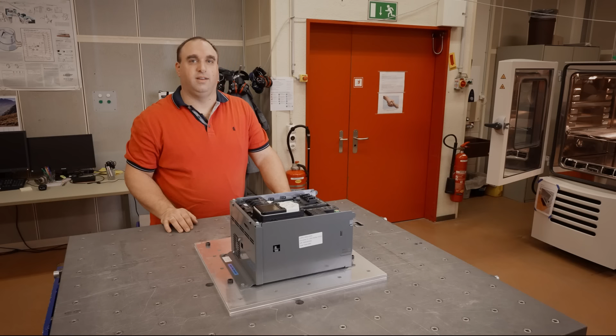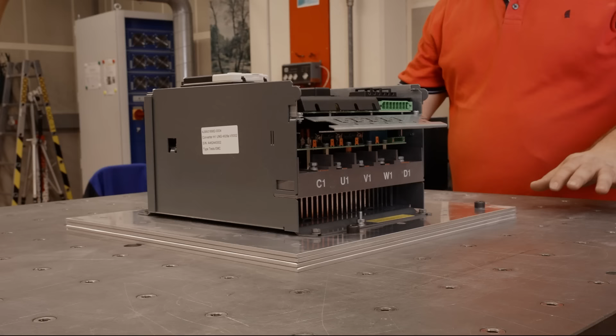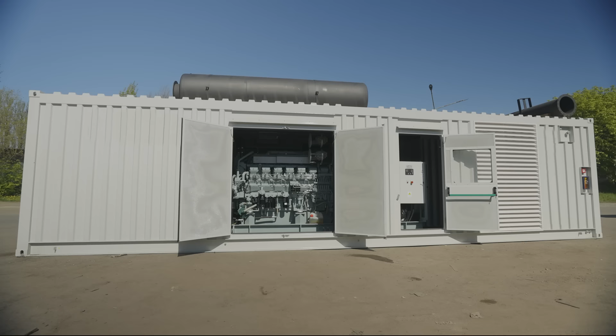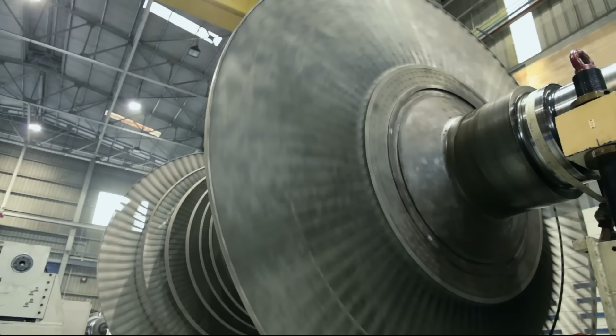We have to secure it here, like our customers will do in the power plant, so it's the same as installed in the power plant. Every axis is tested, and we test it for mechanical resonances, and whether it survives or any parts get loose. We test it because sometimes these devices will be mounted near the big machines, and the machines always vibrate. Also if you have a floor, you get little vibrations too, which can be bigger or slower.